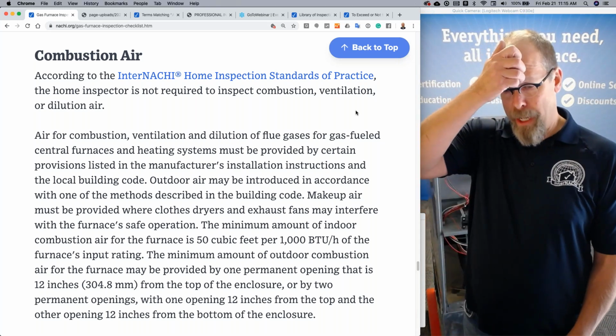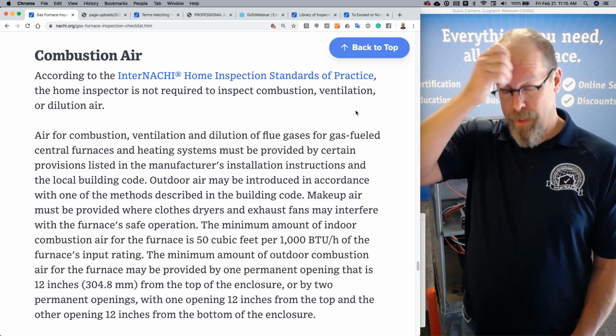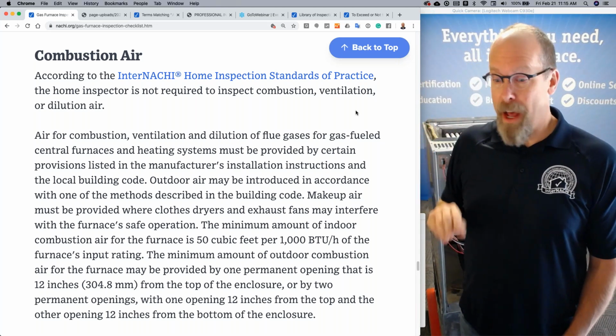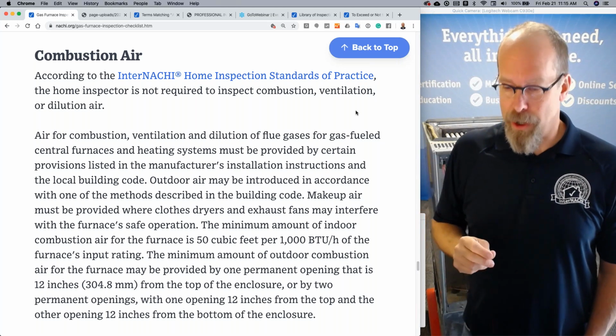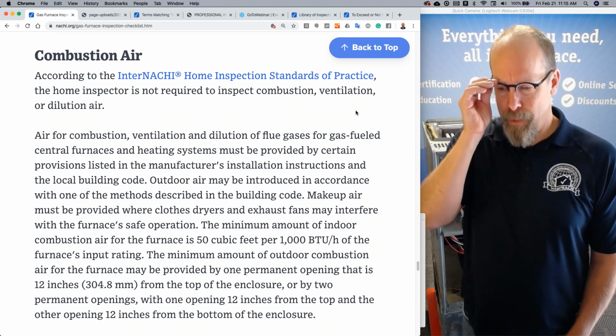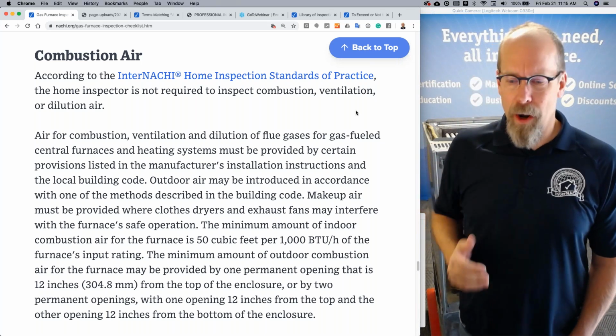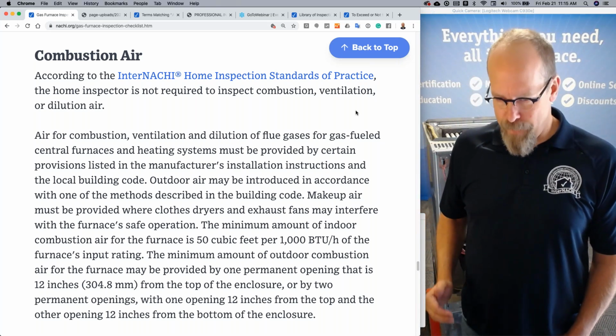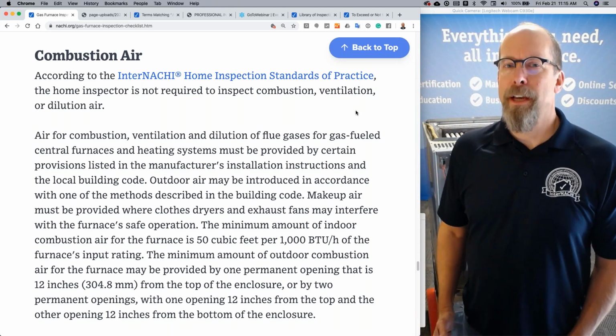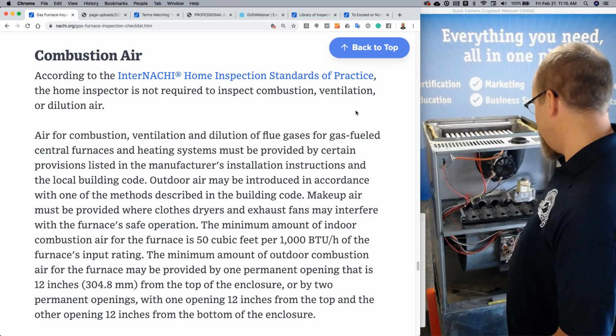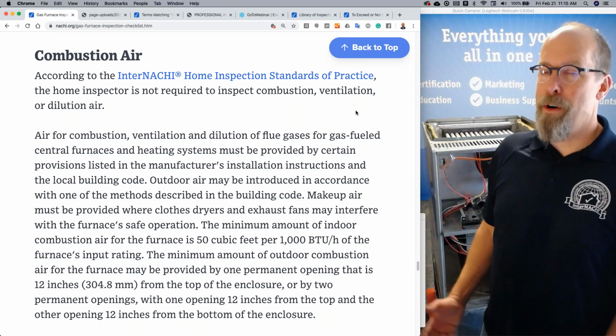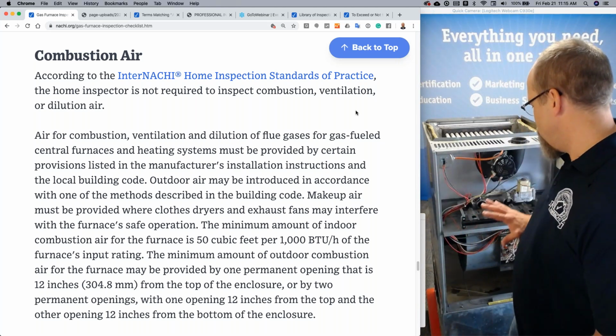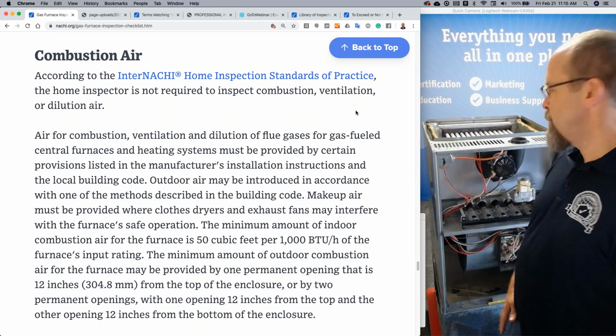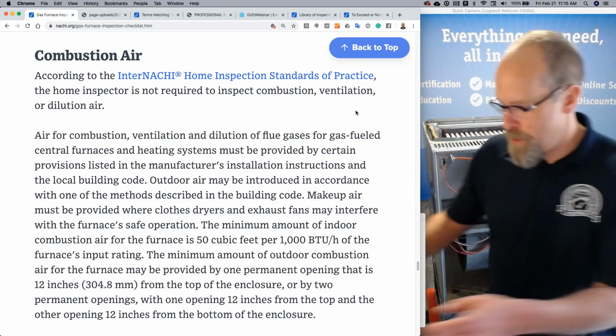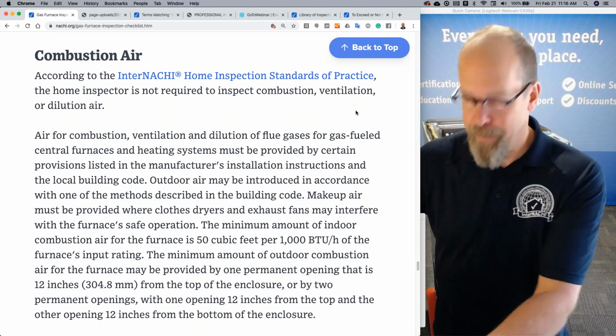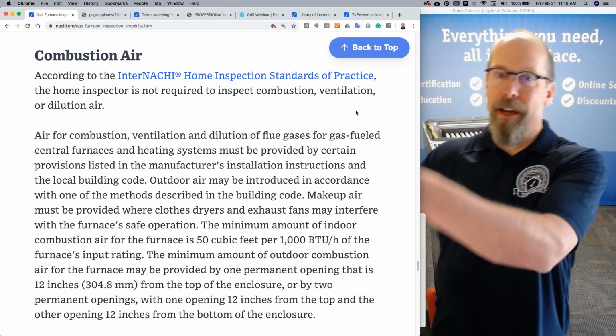I'm concerned with that when I go into a small laundry room or utility room, and I've got those three things. I've got a clothes dryer, an exhaust fan, right? I have a hot water tank, and I have a furnace that needs air, like this fella, right? High efficiency, category 4, I'm not too concerned. But this one is drawing air for combustion, right in there. And it's competing with other things that are depleting combustion air.